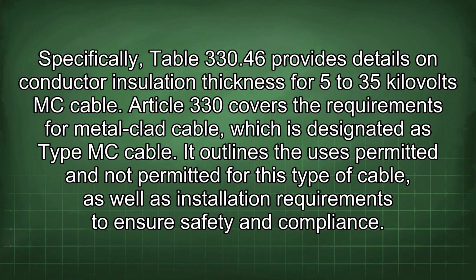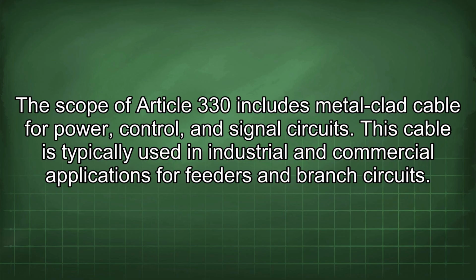Article 330 covers the requirements for metal-clad cable, which is designated as Type MC cable. It outlines the uses permitted and not permitted for this type of cable, as well as installation requirements to ensure safety and compliance. The scope of Article 330 includes metal-clad cable for power, control, and signal circuits. This cable is typically used in industrial and commercial applications for feeders and branch circuits.